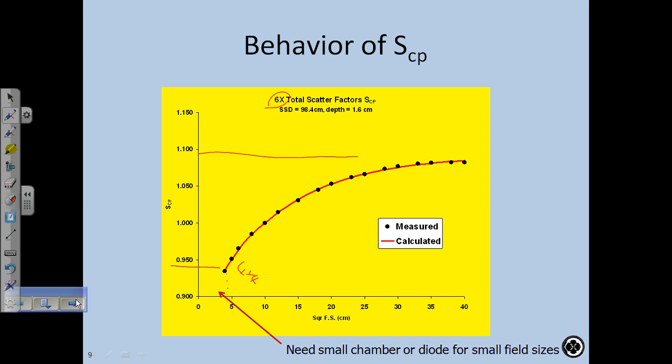We also know that for charged particle equilibrium, we need scatter around the chamber, so we need a little bit of margin around the chamber. That limits the minimum field size that we can measure with that chamber. So we can use a smaller chamber, and that'll help us get down to maybe 2x2.